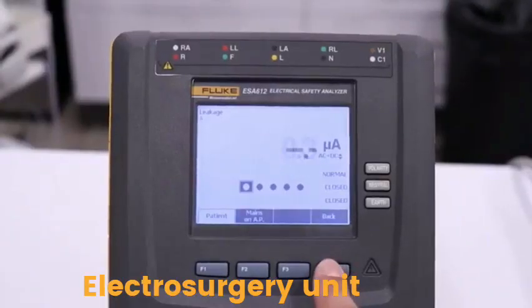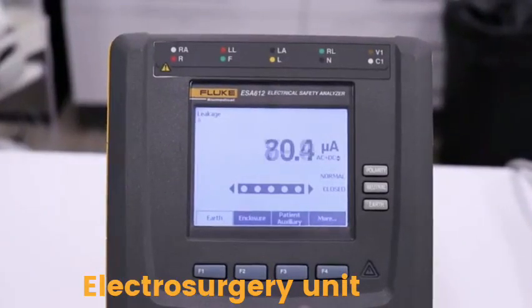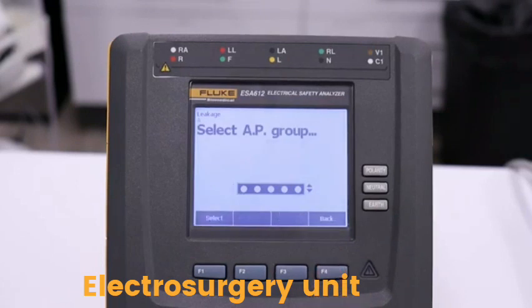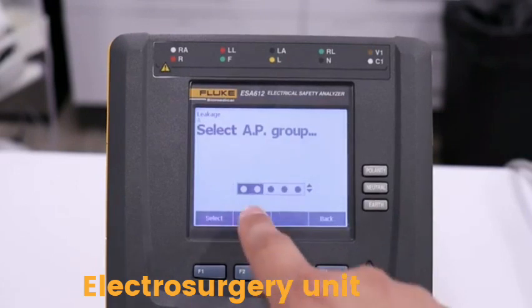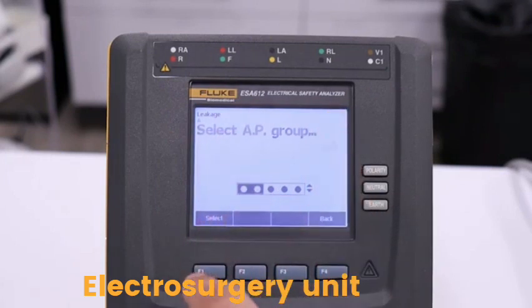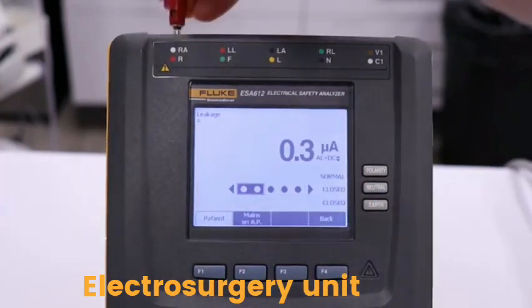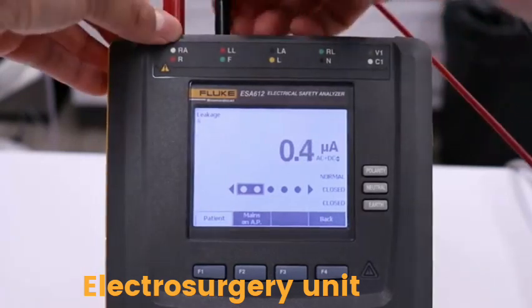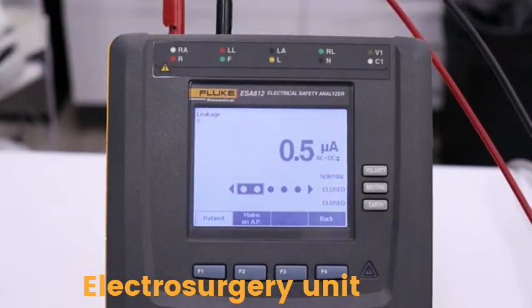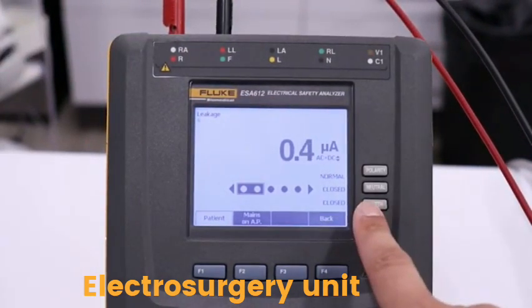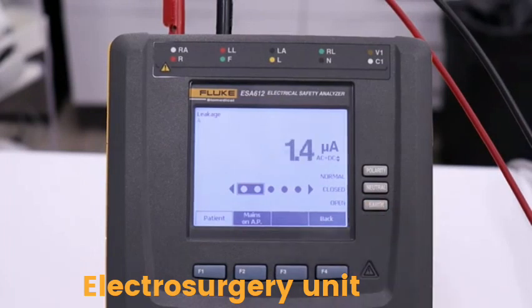Go back to the leakage menu on the ESA by pressing F4 and then F4 again. This time, we will select the first two applied parts since we are testing with two separate leads. Plug both test leads into the first two receptacles on top of the ESA. Test for normal polarity, closed neutral condition, and single fault open earth condition.